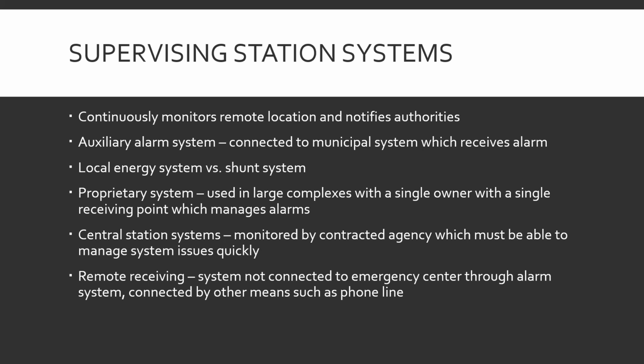And the shunt system does use the municipal circuit. That's, like I explained earlier, the system tells dispatch, hey, there's a fire alarm, page the fire department. Dispatch goes, okay, we have an alarm, go here.